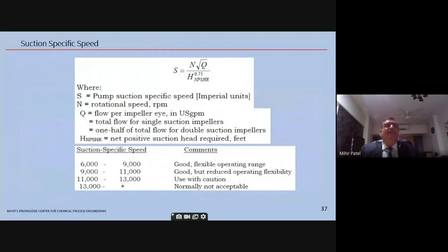So this is the suction specific speed. Now, suction specific speed indicates the suction characteristic of the pump. As you can see, the formula is S equal to N root Q divided by NPSHR to the power 0.75. Now, in any pump, in a FEED stage engineering, let us say you are asked to give the other disciplines the height of the suction vessel, how high it has to be, whereas you don't have any reference to vendor interactions, and you are not sure exactly how much NPSH is available to give to the pump. So at that stage, this particular formula comes in good use.